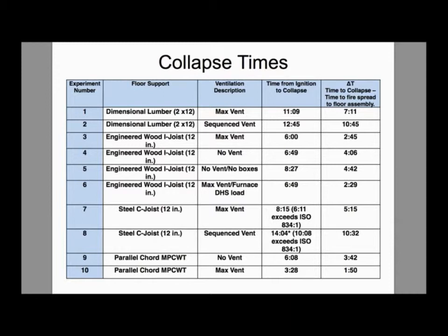The steel joists, 5 minutes and 10 minutes. Parallel chord trusses with no vents lasted almost 4 minutes, with maximum vent less than 2 minutes after they caught fire. All of these times are within your operational time frame. There is no 20 minutes of safe time. It's just not there. Where did it come from?